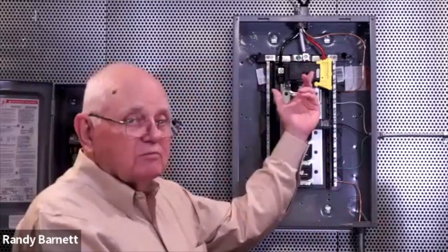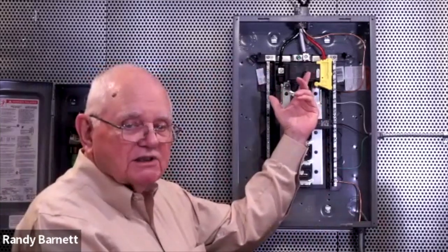It says in service equipment, barriers shall be placed such that no uninsulated, ungrounded service bus bar or service terminal is exposed to inadvertent contact by persons or maintenance equipment while servicing load terminations with the service disconnect in the open position. So even though I've turned the service disconnect to open, once again, we're energized.